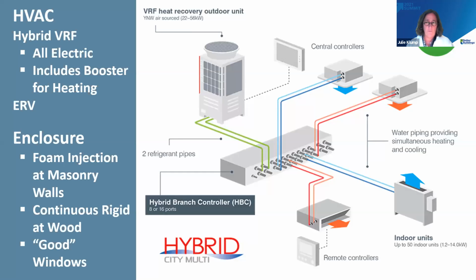The exciting thing here, as a way to minimize refrigerant in our buildings, is we're going to install the Mitsubishi hybrid. It's basically a VRF unit with refrigerant that runs to a branch controller, and from the branch controller it becomes hydronic. So in each unit there's a vertical fan coil, not unlike what they have now — distribution of cooling and heating will be the same, but we've minimized refrigerant and gone all electric. We're super excited about this.